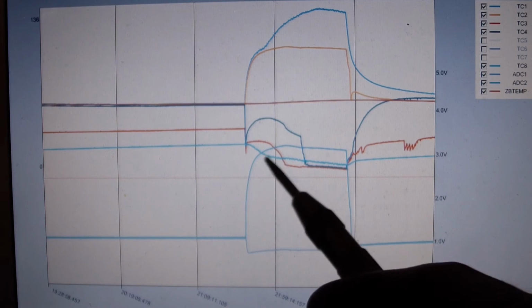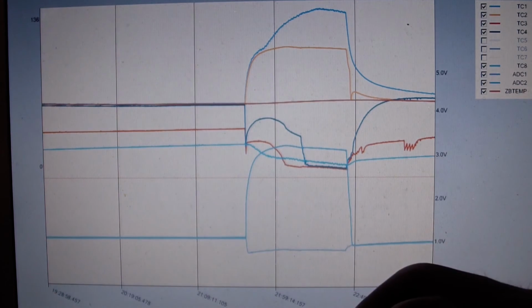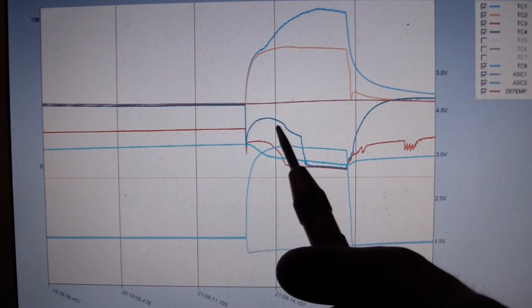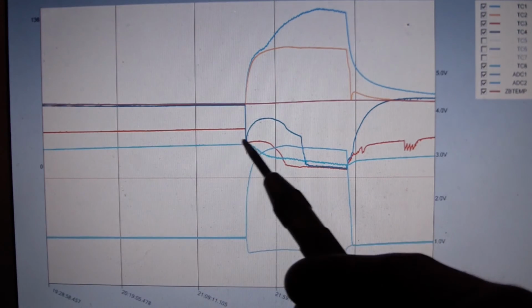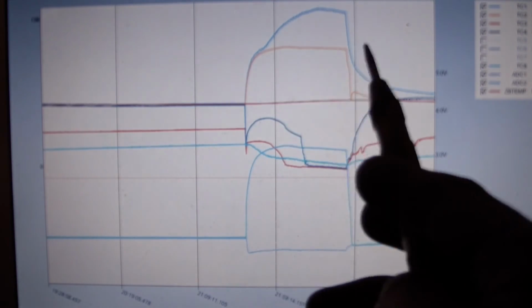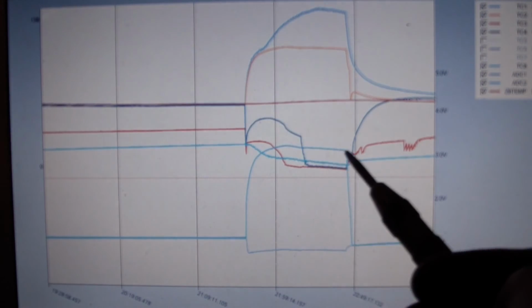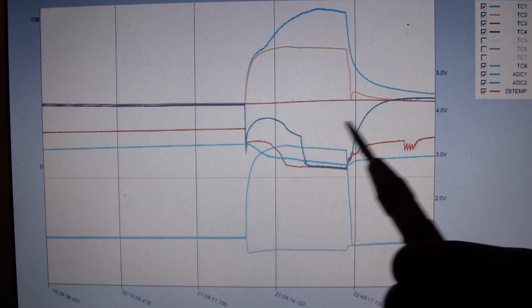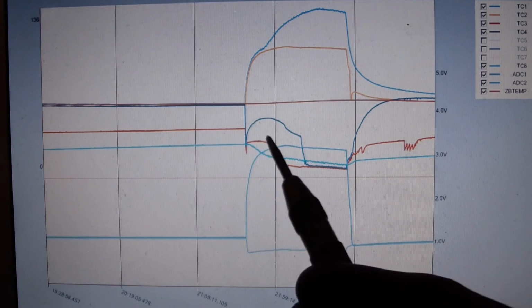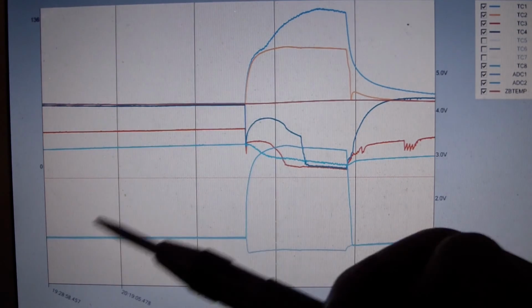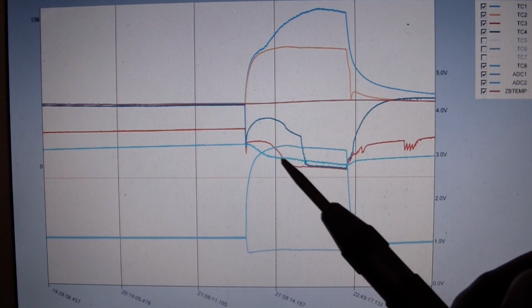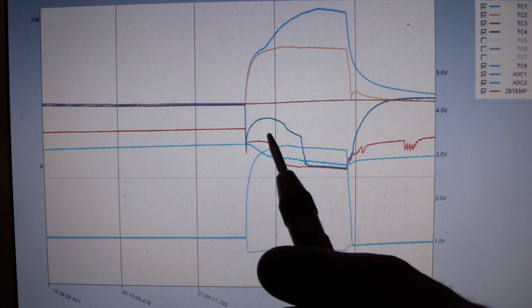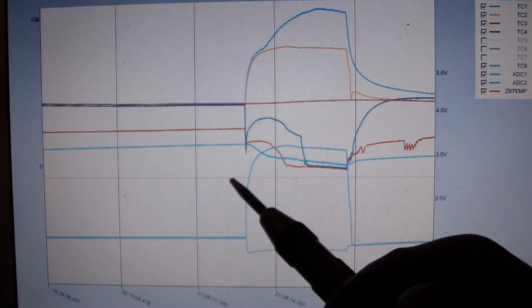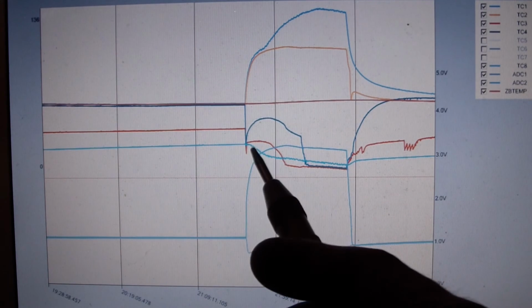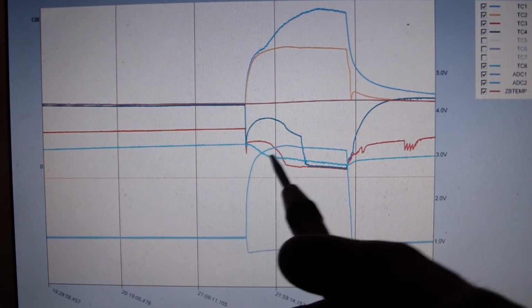We can install a heat interchanger like I did, not only for the purpose of trying to protect the compressor from a slugging condition where it's pulling liquid back, but we also have to consider the possibility that we can bypass some of that heat energy that wasn't dissipated properly in a subcooling fashion in the condenser. We can bypass the evaporator and go straight to the compressor with that enthalpy to be dissipated, again in the condenser, rather than just flash that off either in the capillary tube, which creates choked flow and we have reduced mass flow rate, or spitting that warm gas into the evaporator where it eventually has to pass back to the compressor anyway. So it's a nifty way to transfer some heat and bypass the evaporator. However, I think the drawback of it is the initial pull down, getting into equilibrium, takes longer.